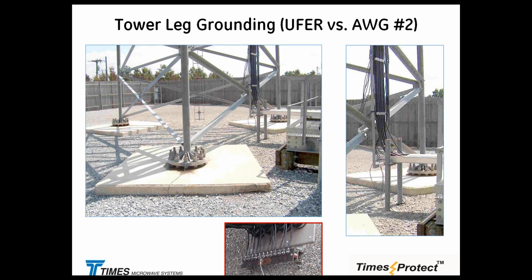Coaxial grounding kits. If you take a look at the coaxial grounding kits, the fact that the kit came with 2 meters worth of wire doesn't mean that we have to utilize this whole wire, okay? Cut them short, cut down on the impedance and inductance of that grounding kit. That's how you are removing basically the current from the shields. And this is not even that bad, what we are looking at right here, where they utilize the whole length of the grounding kit. I have seen them nicely wrapped in a tight coil, basically with a plastic tie hanging happy on the side of the tower, providing huge impedance and more inductance for stripping of that current from the coaxial shield.